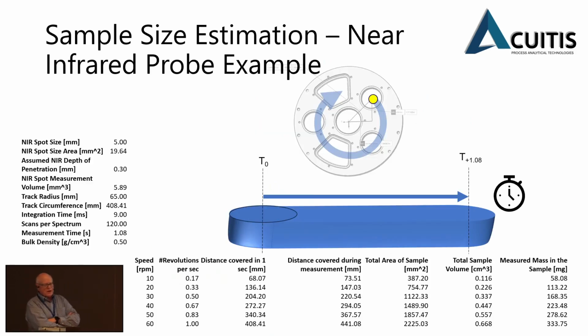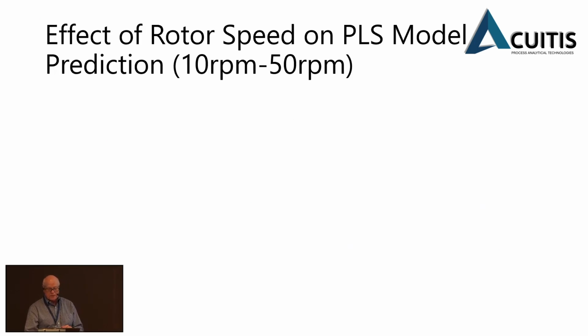So if you look at the sample size that we're taking, if you stretch it out, it is a curved oblong, if you like. And here, Phil did some calculations on the contributing weight, how long you're scanning and how fast the paddle is moving. So this is all specific to the speed of rotation of the paddle wheel in the feed frame and how long you're scanning for. And you can use this to estimate sample size against how long you scan, against how long the powder is moving. So this is just an estimation, but the best thing to do is to empirically measure it and know that you're setting the fiber optic probe up to be successful.